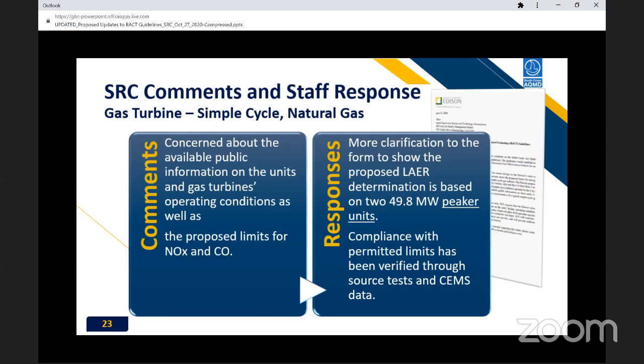What about the ammonia slip test? What I'm trying to say is, when we first submit a permit application, we do an initial performance test. When the catalyst is fresh, it's easy to meet the low NOx limit and low ammonia slip limit. But the efficiency of the SCR decreases over time, so at the end of the catalyst life, would that unit still meet the NOx limit and the 5 ppm ammonia slip limit?